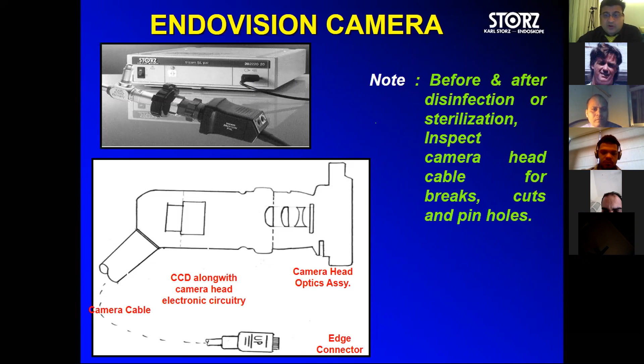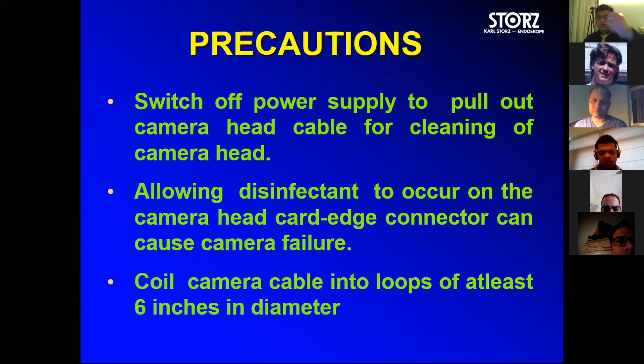And also I told you that if you have a light cable, try to roll it in a bigger fold. Do not twist and turn your light cable. If you do twisting and turning, inside the light cable, there are 16 to 24,000 hair-like fiber bundles. So by continuously twisting and turning, you are actually breaking these fiber bundles. So if they are broken, you can still get a light when you connect with the endoscope, but it is heating up. And the surgeon says, I'm holding for 2-3 hours, I feel too much heat in my glove. So this is why it happens.